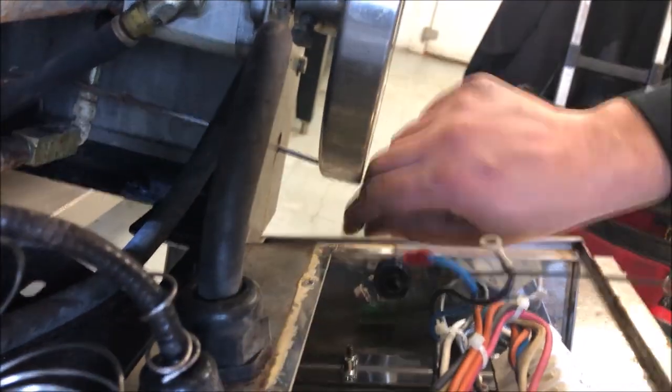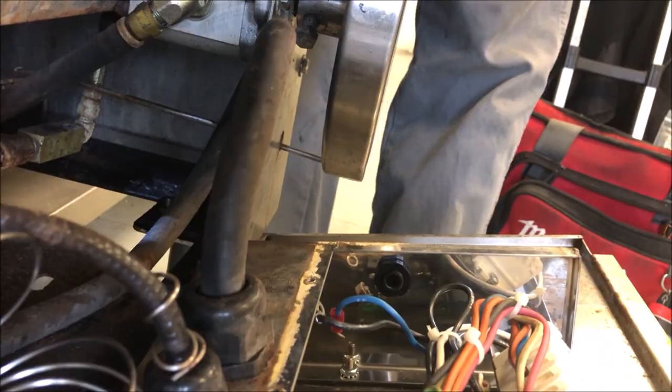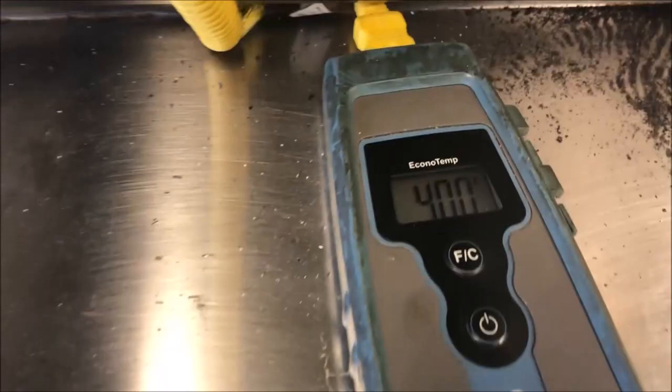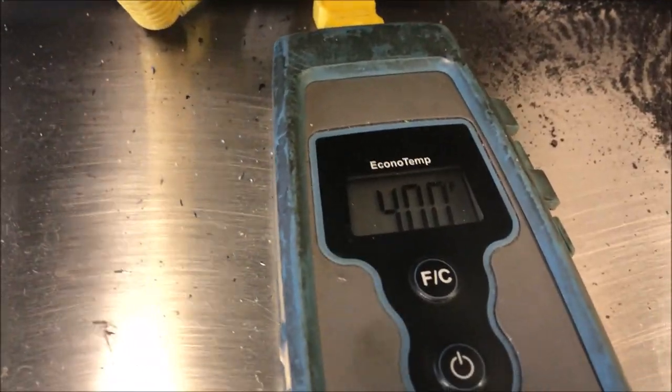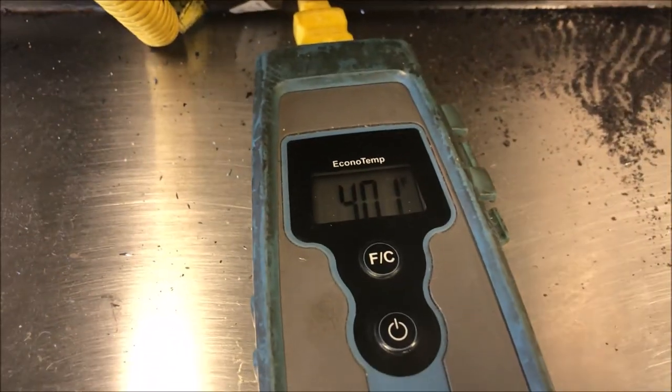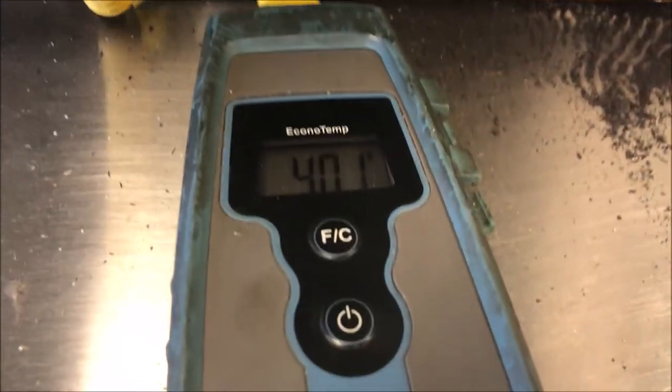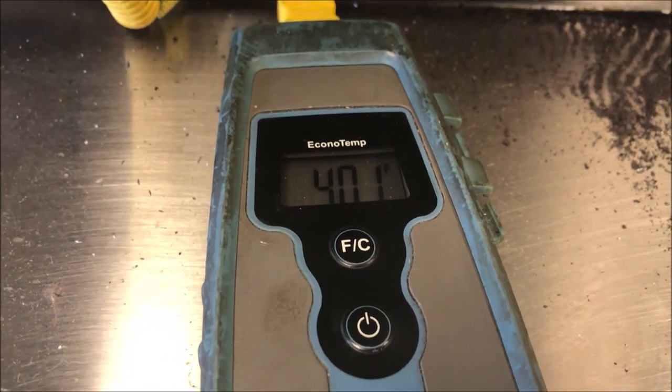The last thing we're going to check is make sure the unit shuts off. So I set it to 400, our heat light has come off, we're not tripping our high limit, everything's all good here.